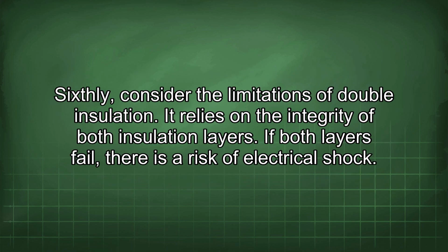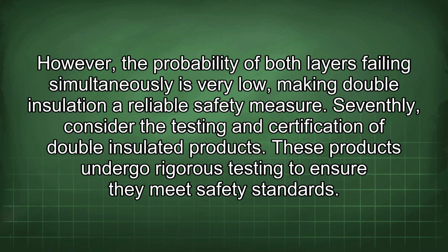Sixthly, consider the limitations of double insulation. It relies on the integrity of both insulation layers. If both layers fail, there is a risk of electrical shock. However, the probability of both layers failing simultaneously is very low, making double insulation a reliable safety measure.